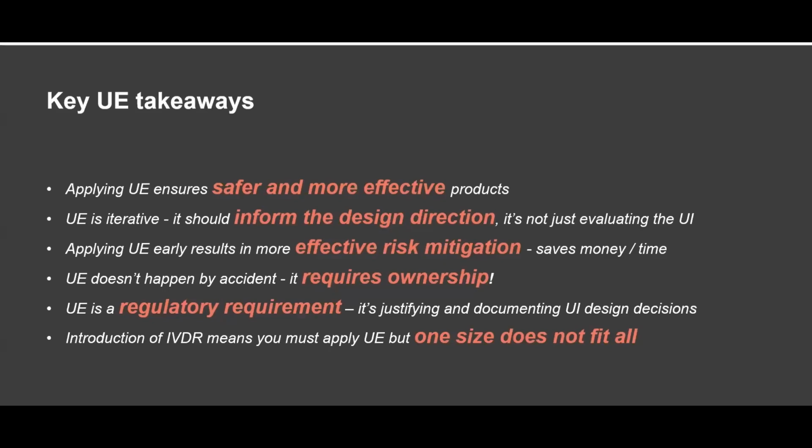It doesn't happen by accident. It requires ownership, and it requires an independent champion to wave the usability engineering flag throughout the development process to make sure you're involved in key design decisions. It's a regulatory requirement, and it's about justifying and documenting the interface decisions, the design decisions that were made or weren't made, and providing justification for why you didn't go a particular route. And the introduction of IVDR means that you must apply usability engineering, but one size does not fit all. So not every program is the same, and you need to determine what's appropriate for your program.